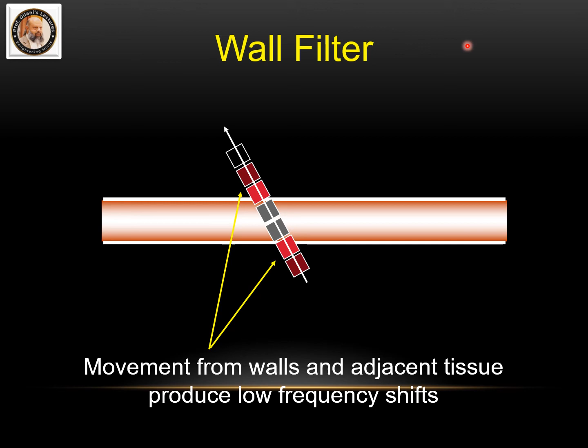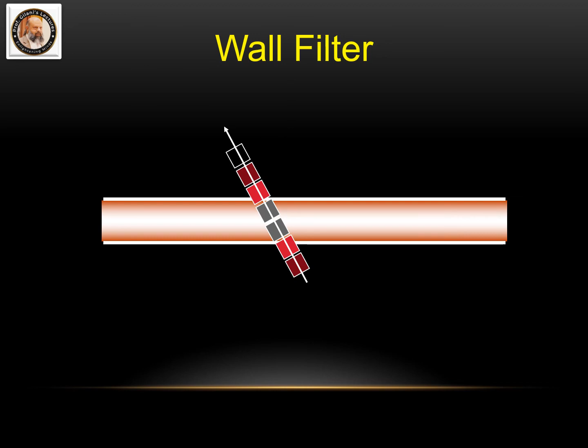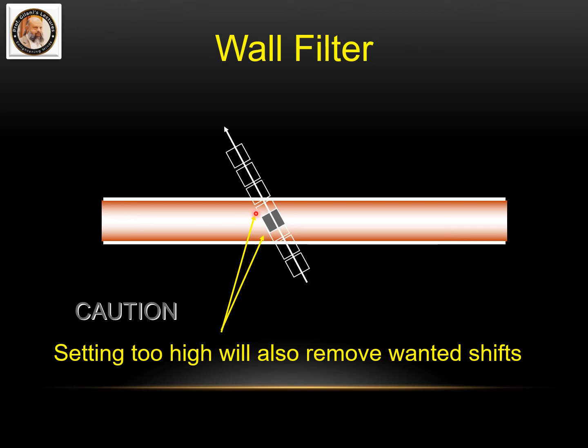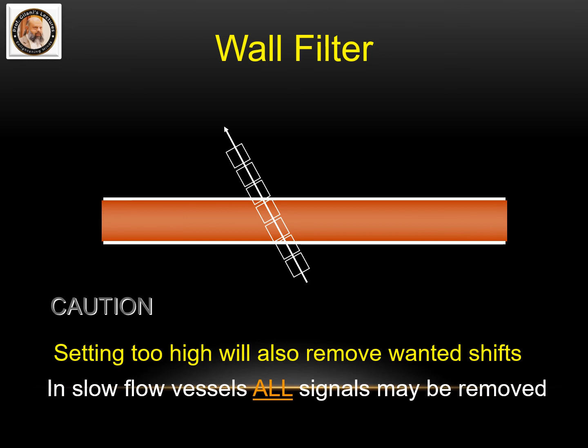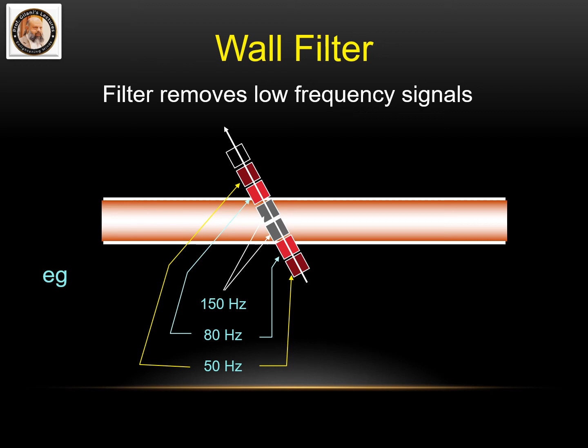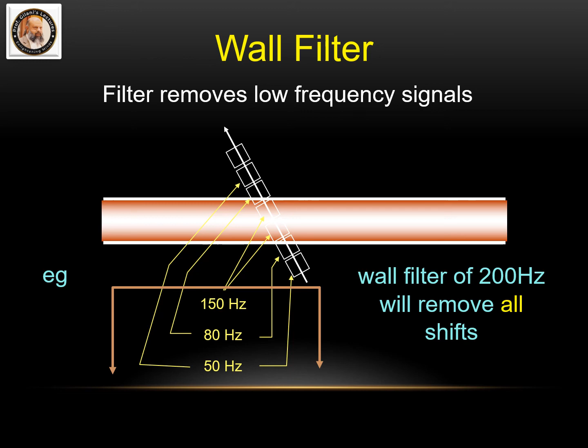So, the wall filter in ultrasound is a way of filtering out low or high frequency Doppler signals in clinical ultrasound. It is usually used to filter out very low frequencies that may add noise to a spectral Doppler waveform. But if we set the wall filter too high, it will also remove the wanted shifts. So we have to keep it appropriate. Here we can see the appropriate is 150 Hz in this condition. We need to remove these red ones, which will bring information from the wall. A wall filter of 200 Hz will remove all shifts.